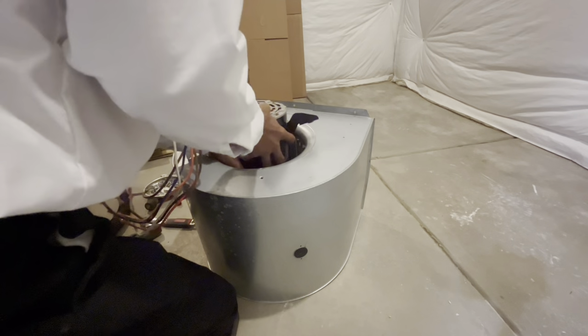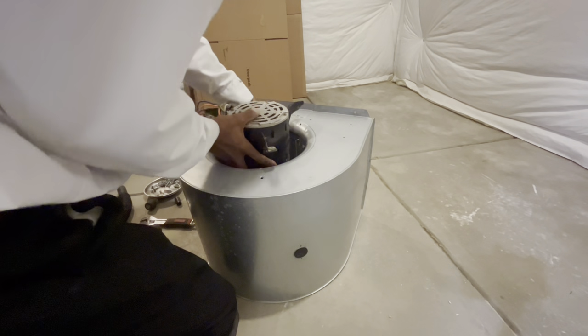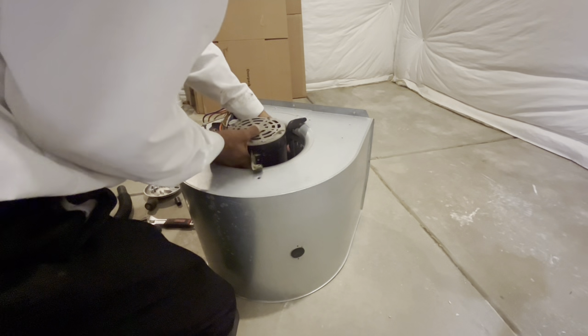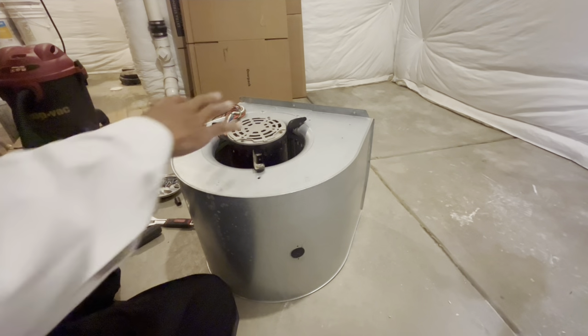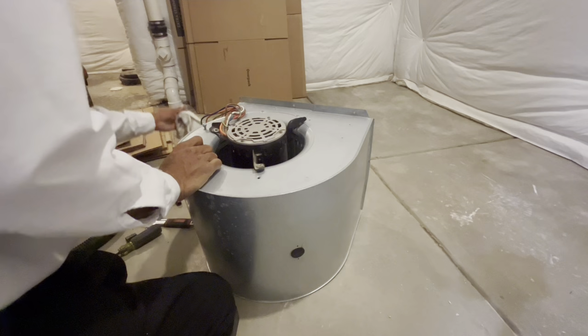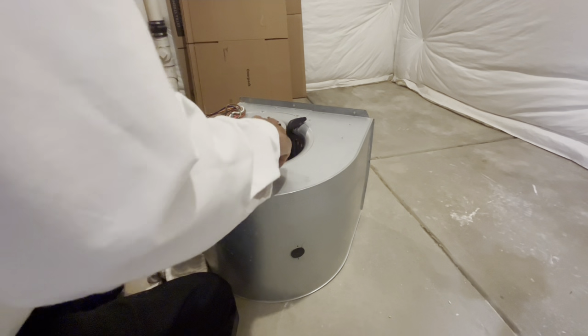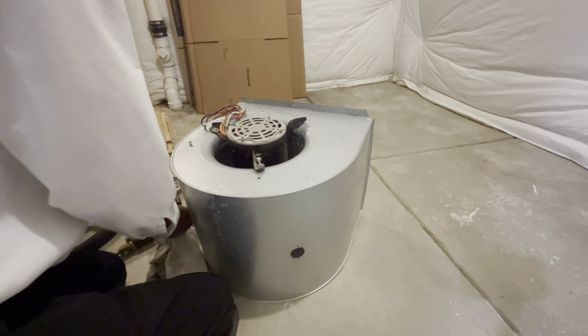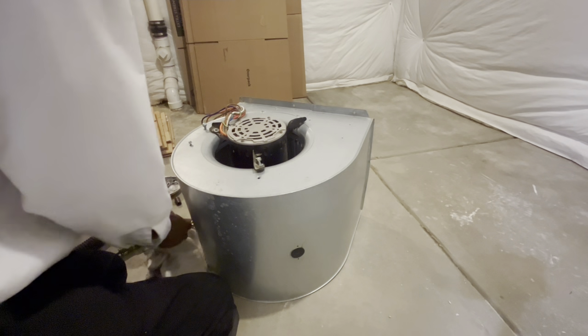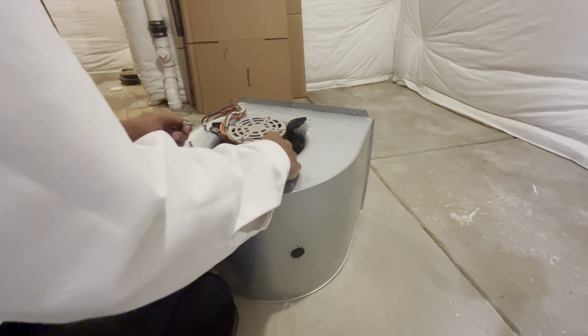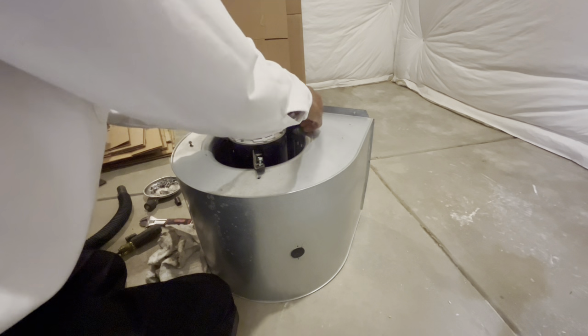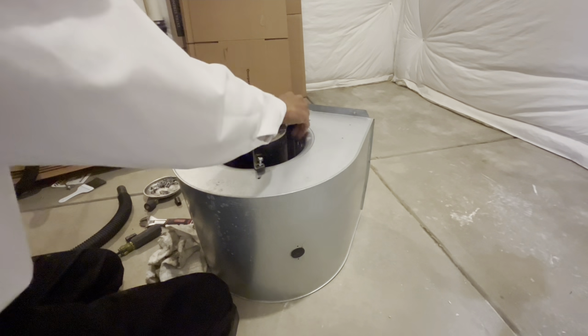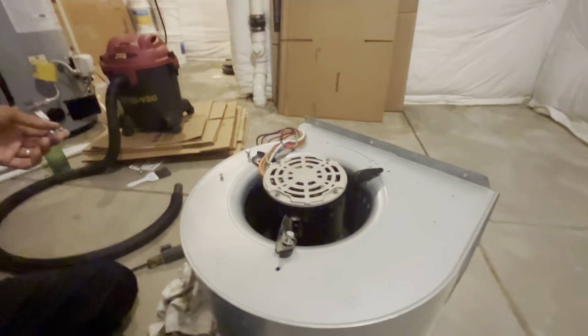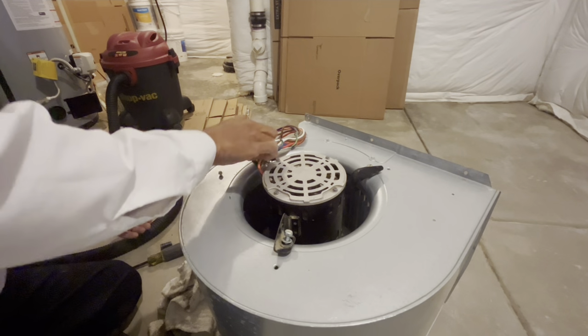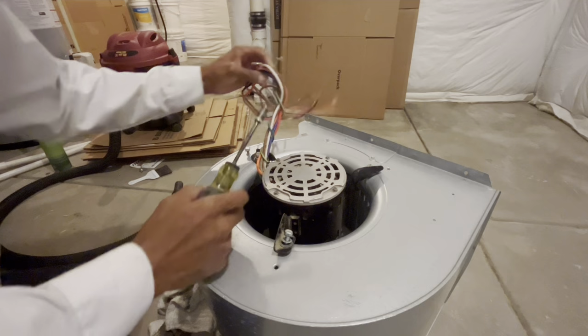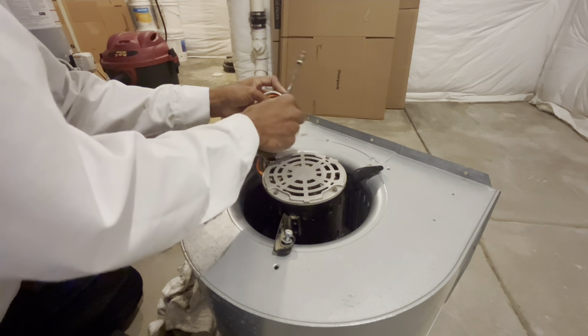So now we've got the blower housing and the wheel all clean. The motor has been cleaned by hand, and I've taken my shop vac and blown all the dust out. So now I'm in the process of reassembling this lower portion of the furnace, and I use all hand tools. I treat the equipment like it's a Ferrari or Lamborghini. That's something that's built by hand. I do not want to use power tools that may strip out bolts, anything like that, because then you strip out a bolt, then something gets loose, then something makes a noise, then something gets off balance, then it just throws the whole system off.